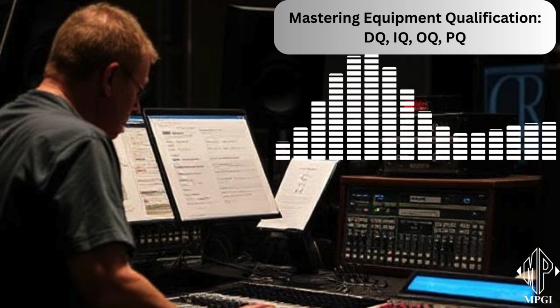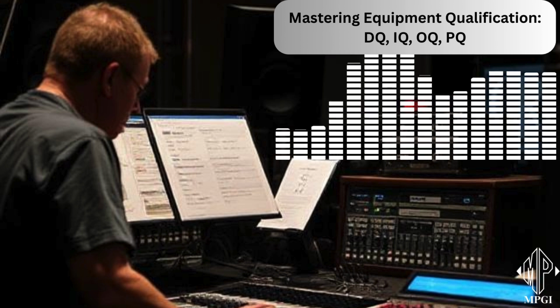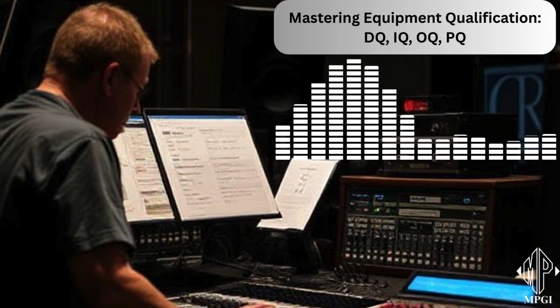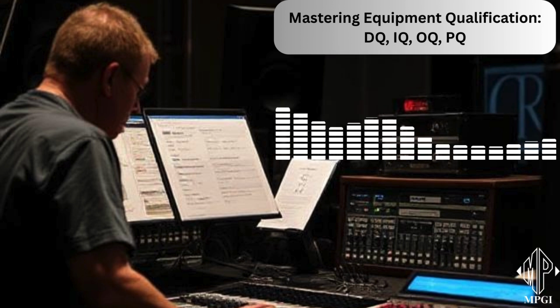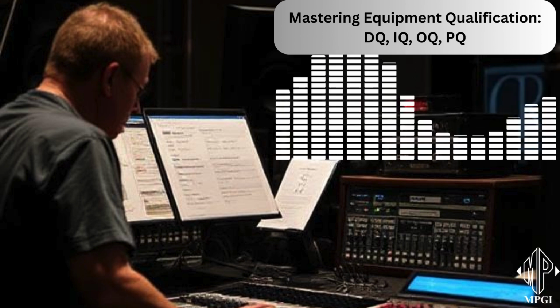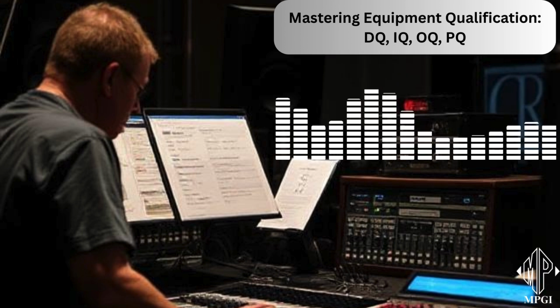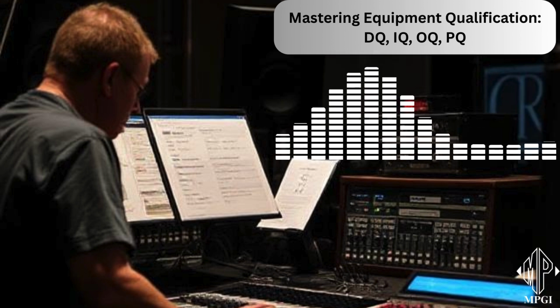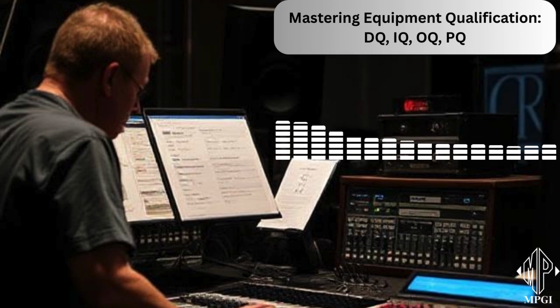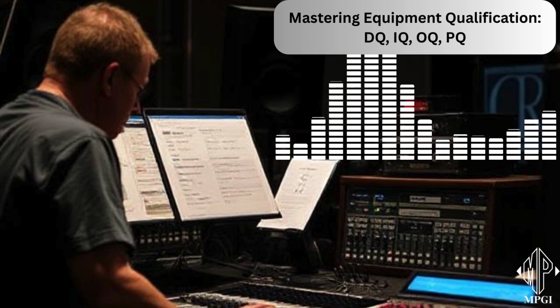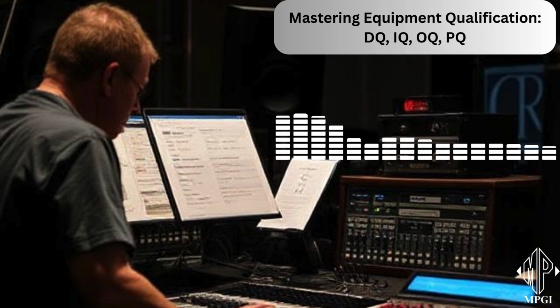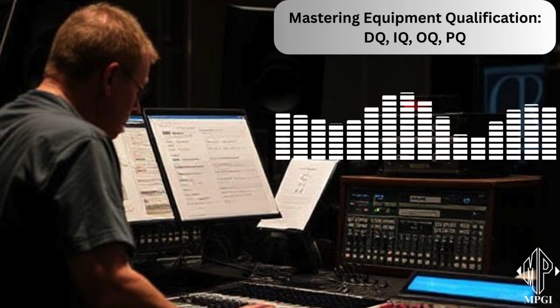What about the documentation for PQ? Is it similar to the other stages? Yes, it follows the same pattern. You've got the PQ protocol outlining the objectives, scope, and test procedures. Then the test plans and procedures with those detailed instructions. And, of course, the test records and data capturing all the results from each run. Meticulous record keeping, as always. Right. Calibration certificates are essential for any equipment used during testing, and any deviations get logged in the deviation reports along with how they were handled. Ensuring full transparency and accountability. Exactly. And finally, you've got the summary report, which provides an overview of the PQ process, the main findings, and conclusions on whether the equipment consistently met the performance standards under real-world conditions.